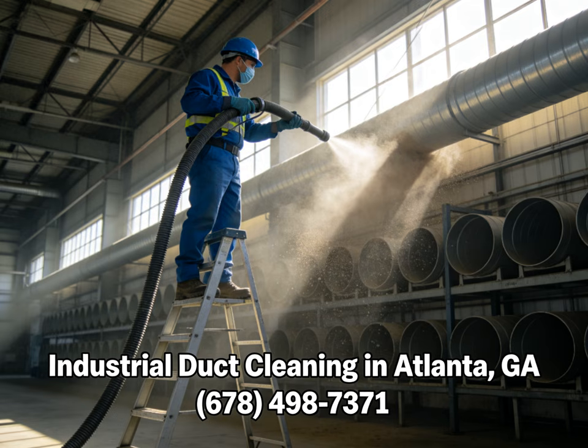The sources use this super formal term, avant-garde methodologies. But let's translate that into mechanical terms. They're basically sending high-speed pneumatic air whips and rotary brushes deep into the shafts. Because we established earlier that the humidity cements the dust to the walls, negative pressure alone wouldn't actually move it. Oh, right. So technicians feed these pneumatic whips down the lines. Powered by high PSI compressed air, the whips just thrash wildly against the interior walls. It is a calculated physical agitation. So they physically break the chemical and mechanical bond between the grime and the galvanized steel.